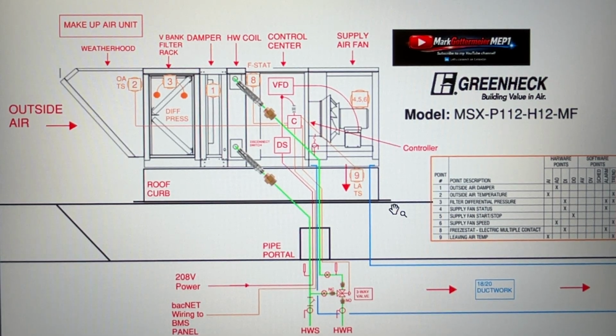In this video, I'm going to talk about a makeup air unit that we have on a current project. The makeup air unit's purpose is to bring in fresh air from outside into a building or space. This unit here has a series of chambers within it that all have certain responsibilities in what it's accomplishing to make it work. So I'd like to break down what each of those chambers does.